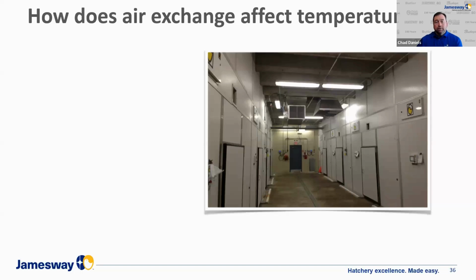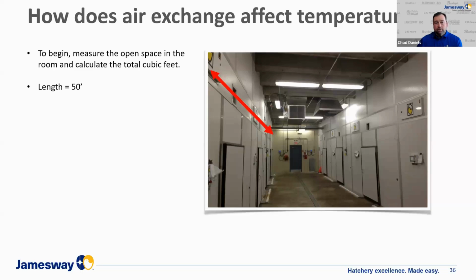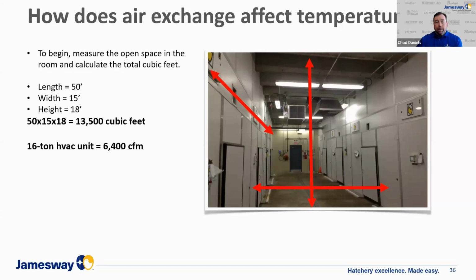To understand that, we use this as an example. We look at a room that is 50 feet in length, 15 feet wide, and 18 feet tall. When I multiply those, I have a total of 13,500 cubic feet of air in that room. Because I have 8 incubators in there consuming a large volume of air, I have a 16-ton HVAC unit on the roof that's moving 6,400 CFM. So with quick math, the air exchange in that room is a 2.11 minute air exchange.